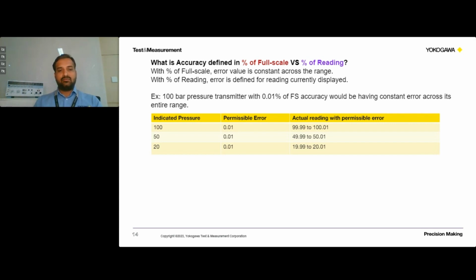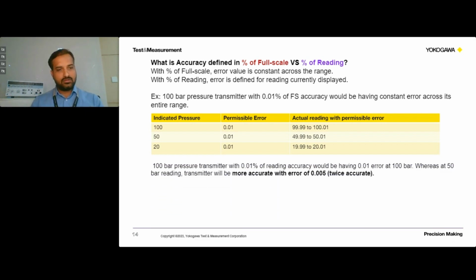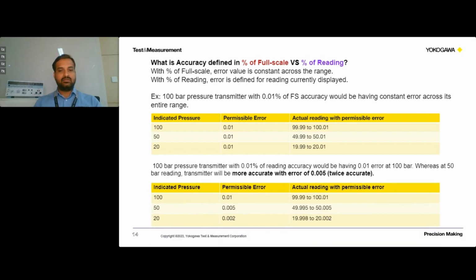And with the constant error, we will have the actual reading with the permissible error. So the range of the reading which we get with the permissible error will be larger with respect to full scale accuracy. Whereas percentage of reading accuracy will give us a better result in comparison to percentage of full scale. We'll be able to have at least 2 times more accurate readings with respect to this example. At 100 bar we will have 0.01 error. At 50 bar we will have 0.005 error. That means we are getting 2 times better results in lower ranges when we have percentage of reading accuracy. So this is the table which explains it.